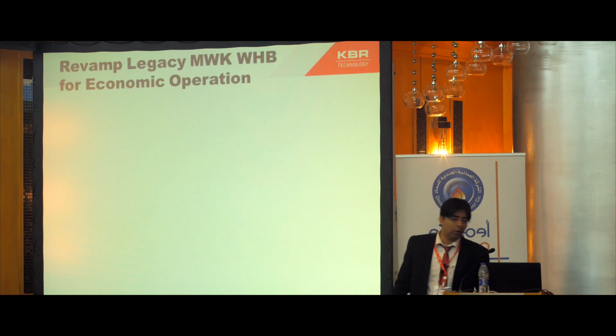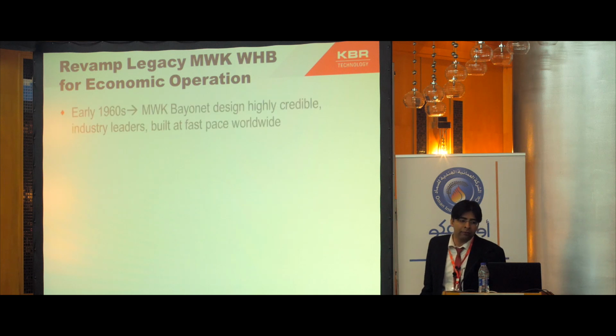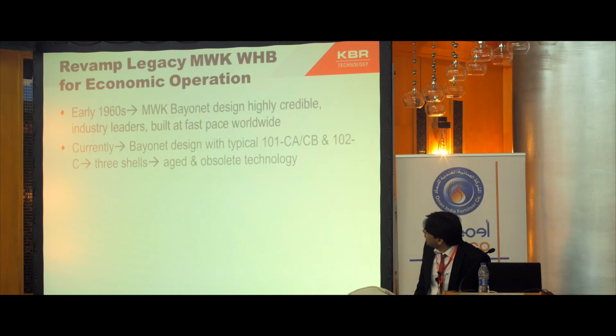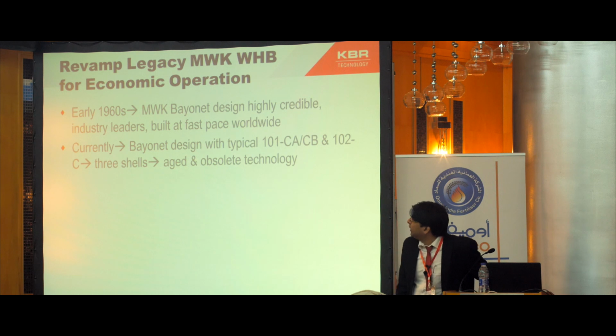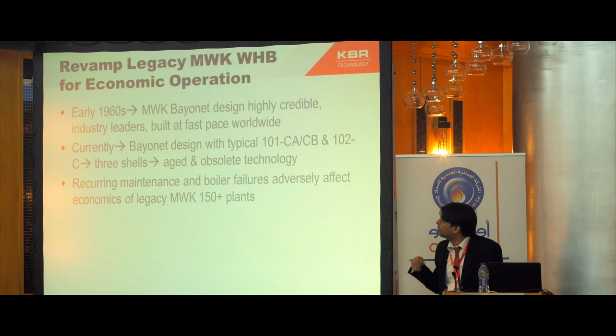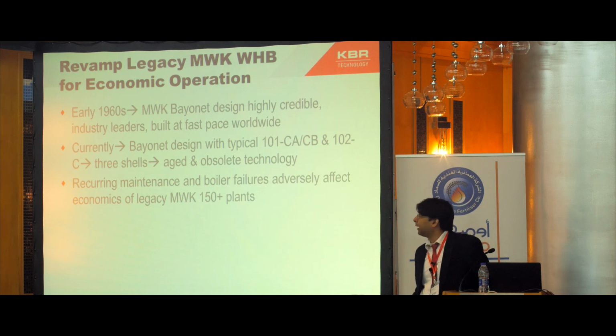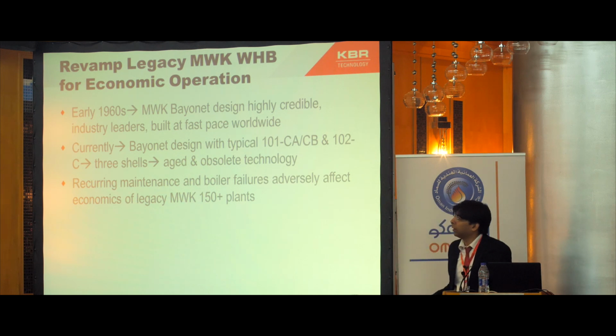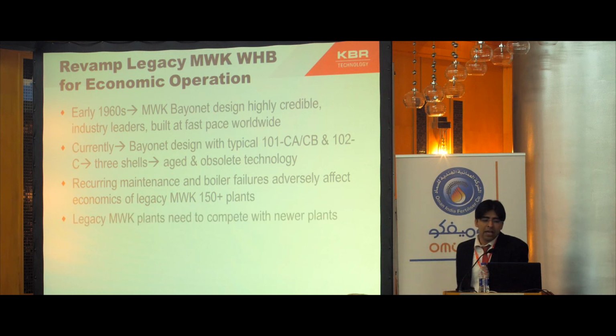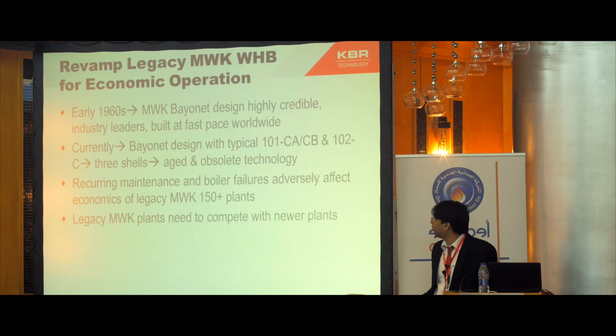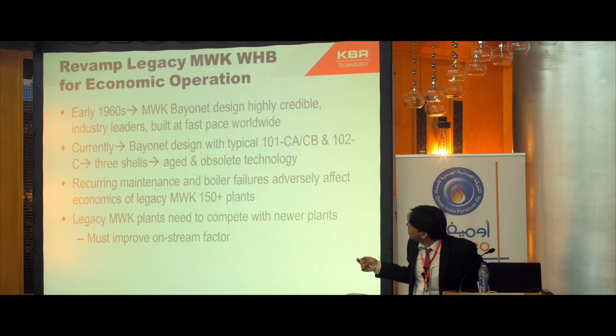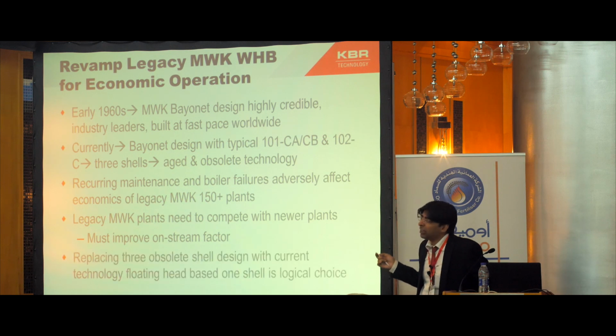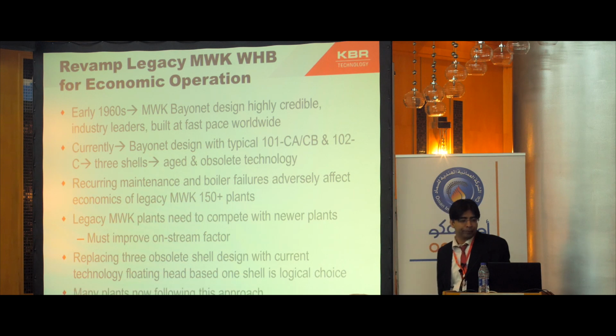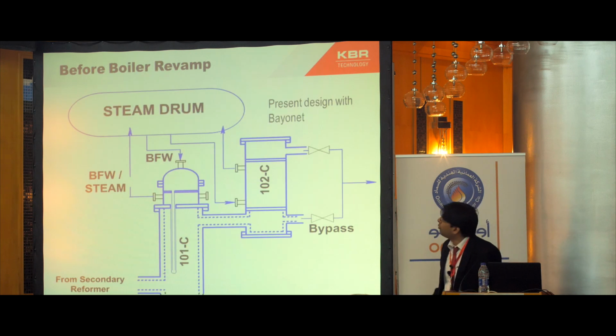Moving on, how can we revamp the MWK waste heat boiler? This bayonet design is aged and obsolete technology, calling for recurring maintenance and failures, which adversely affect the economics of these plants. So to compete with newer plants, replacing the MWK waste heat boiler design with a new floating head design is a logical choice. Many plants are now following this approach.